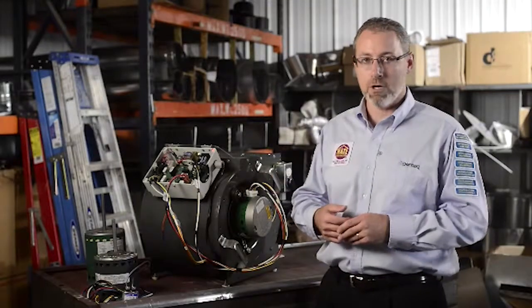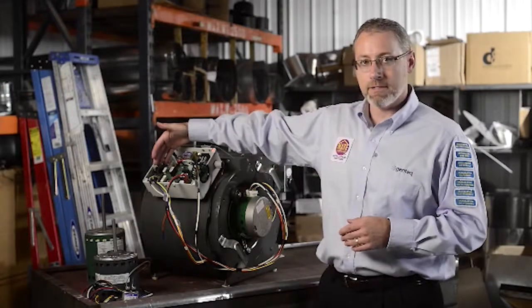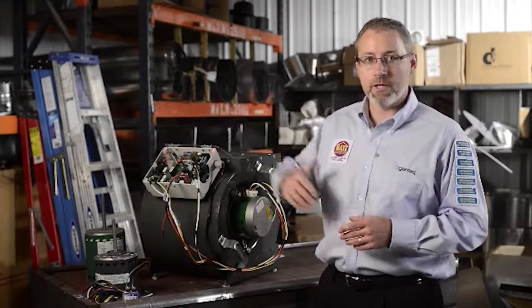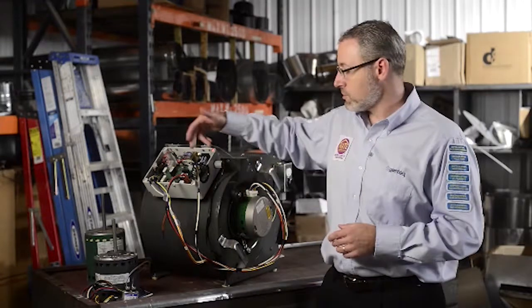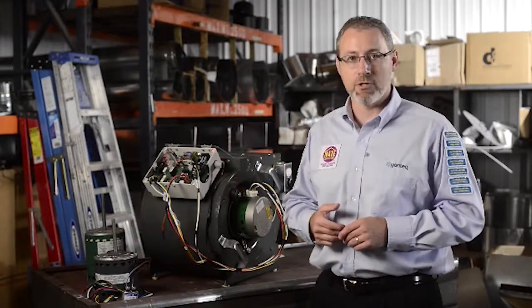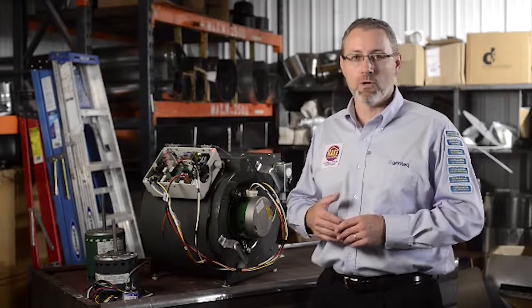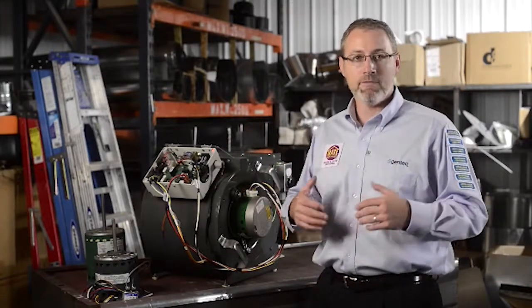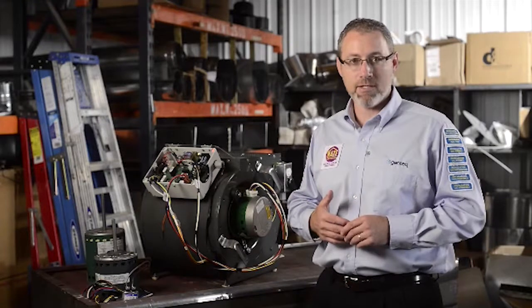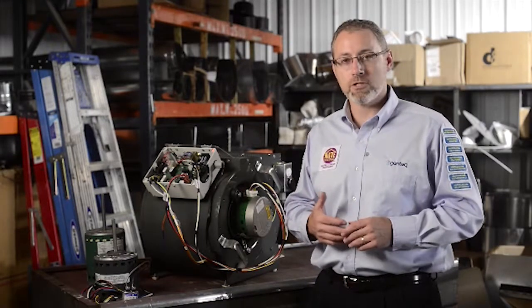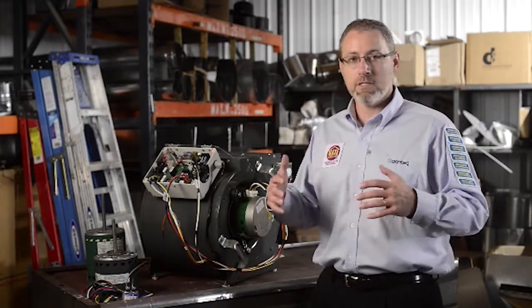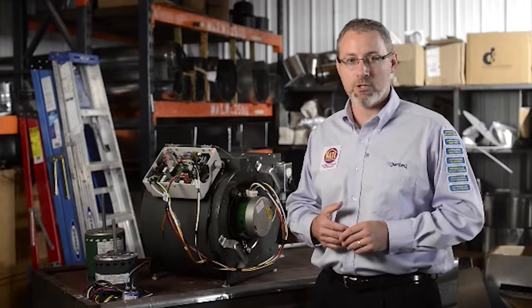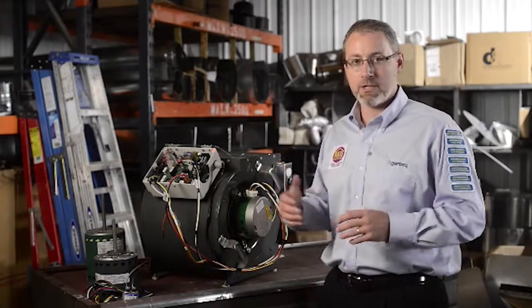the fan relays. So the way any demand call will go is the thermostat will send a demand down to the control board. That will energize a speed tap, but the motor won't turn on until one of the fan relays is energized. So if the control board or separate components have on and off delays, or even selectable or adjustable on and off delays, all of these delays and all of the sequence of operation in the system, the way the manufacturer designed it, are still applicable to the way we've connected the Evergreen IM.